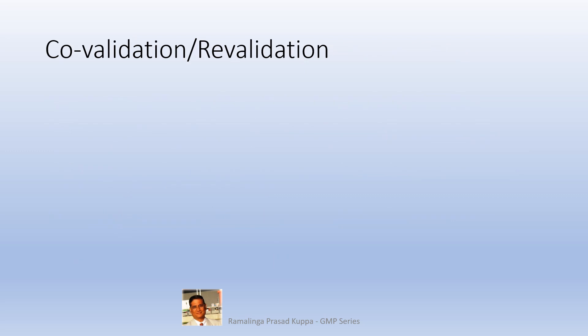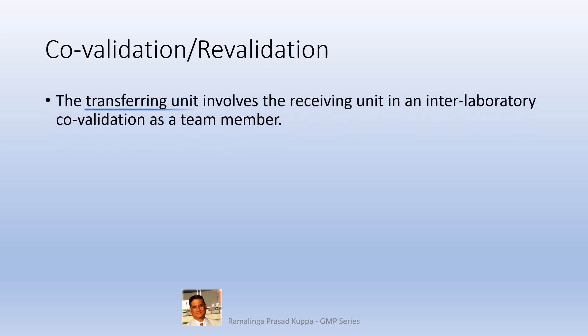Co-validation and revalidation is another approach. The transferring unit involves the receiving unit in an interlaboratory co-validation as a team member. Qualified staff from the receiving unit may be involved along with staff from the originating unit for the method validation project. The receiving unit will be responsible for testing during the entire validation process, which helps to assess the reproducibility of the data. The validation should be done as per USP chapter 1225.